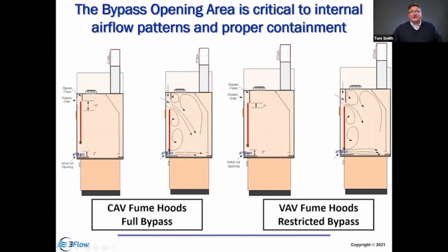I've mentioned the bypass now a couple of times. The bypass is when you close this sash, it opens the area above the sash to allow flow into the hood to help dilute the materials in the top portion of the hood. On a variable air volume hood, this is a restricted bypass. They make it smaller. And now, when you pull that sash down, a smaller amount of air is moving through the top of the hood. If we go too low a flow, it's not going to provide adequate containment, and we're not going to dilute and remove the materials appropriately. So the bypass position is very important. It's bigger on constant volume hoods than it is on variable volume.